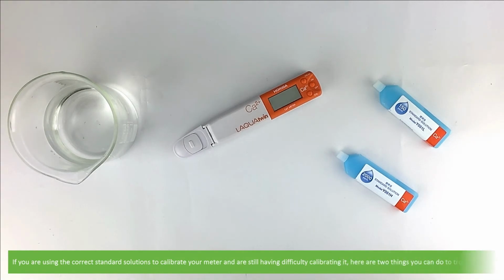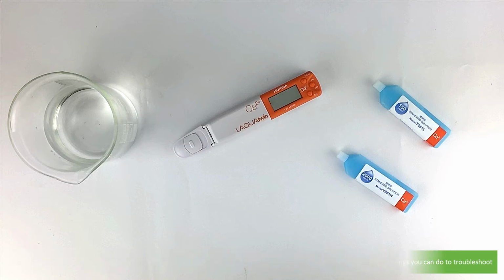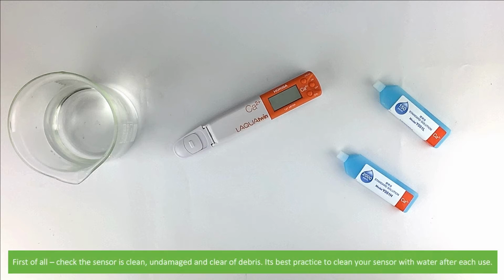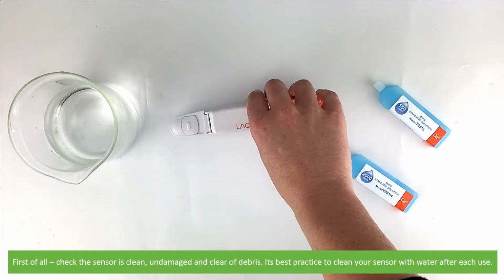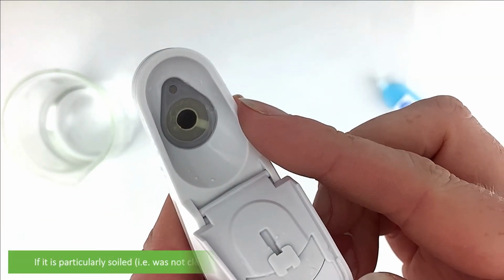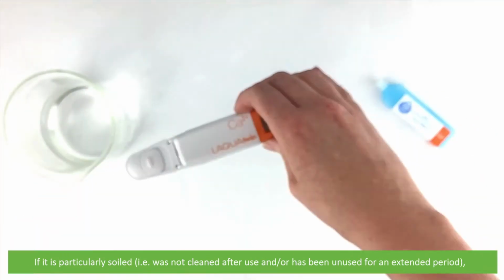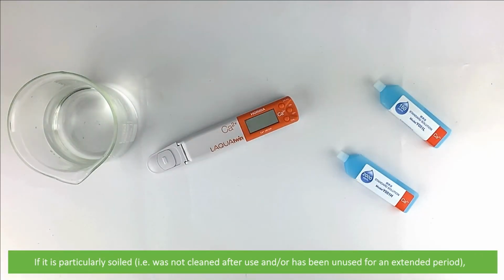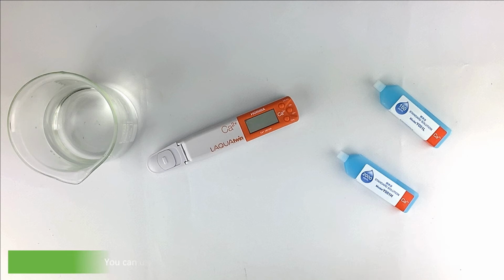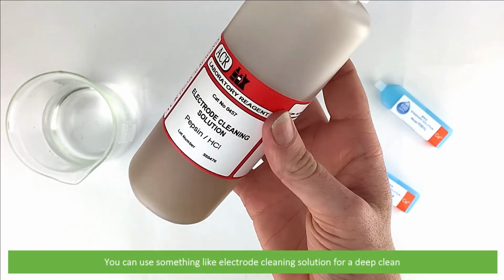If you are using the correct standard solutions to calibrate your meter and are still having difficulty calibrating it, here are 2 things you can do to troubleshoot. First of all, check that the sensor is clean, undamaged and clear of debris. It is best practice to clean your sensor with water after each use. If it's particularly soiled, for example it was not cleaned after the last use or has been unused for an extended period of time, you can use something like Electrode cleaning solution to give it a good deep clean.